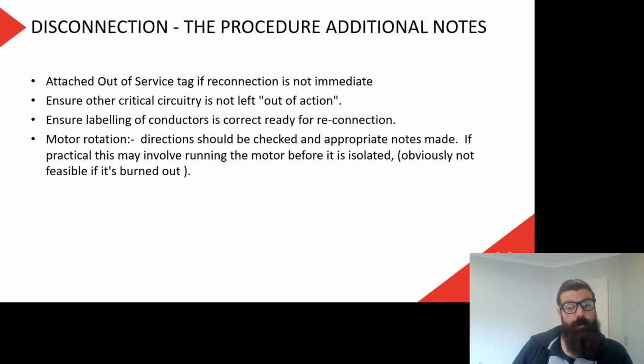Motor rotation. Direction should be checked and appropriate notes made. If practical, this may involve running the motor before it's isolated. Obviously, it's not feasible if it's burnt out. Generally, a motor is going to have a direction that it needs to turn. If it's connected to a piece of machinery, then that motor can only operate in one direction. So if that's critical, then we need to check which way the motor turns before I disconnect it and take it away, because when I put a new one back in, or a repaired one, or maybe I'm reconnecting the same one, I need to make sure the motor's going to be turning in the same direction as it was before.